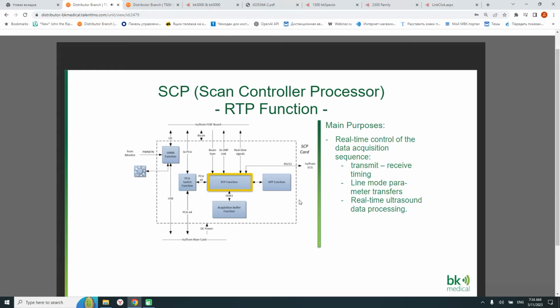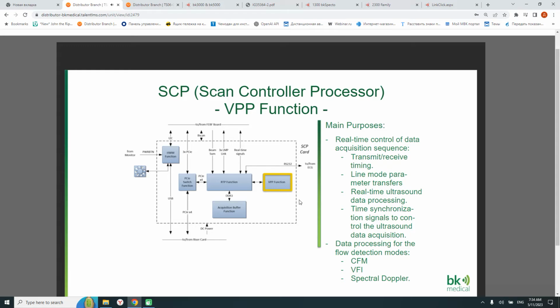The RTP function is a real-time control of the data acquisition sequence, both the transmit-receive timing and line mode parameter transfers, and this is the real-time ultrasound data processing. VPP is a data processing for the flow detection modes like color flow mapping, VFI, and spectral Doppler.